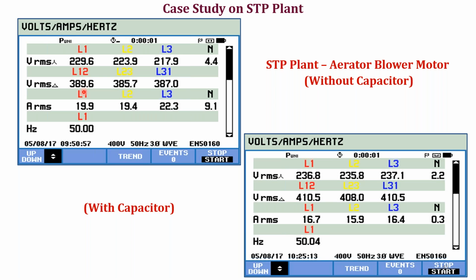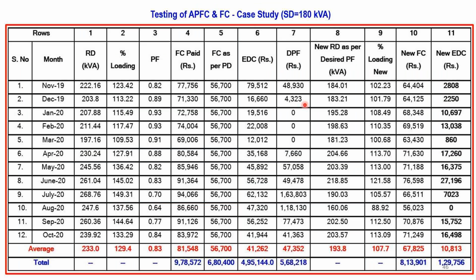Now the current reduction will also affect the distribution line current. So the distribution line current reduction also gives a small amount of saving in the distribution losses, not a very big amount, because we know that the current is going to be carried by the cables, and the cable will have a resistance. So 3 into I square into R into operating hours, that much small saving will also be ensured. So that's why we are insisting to put the proper values.